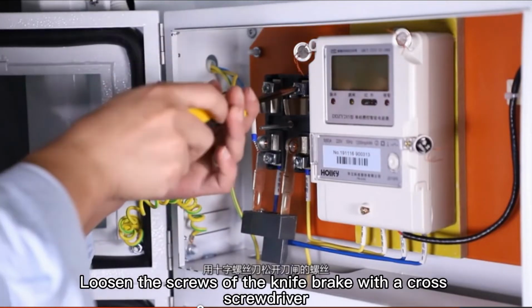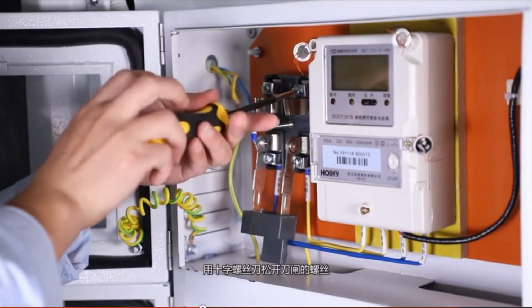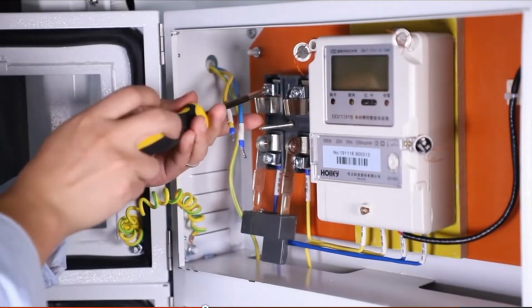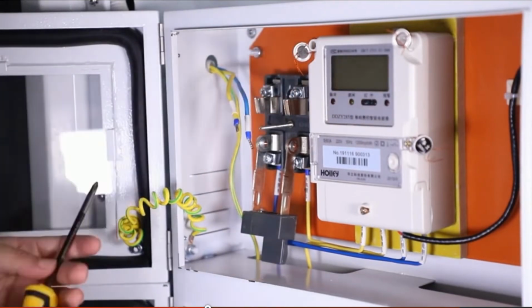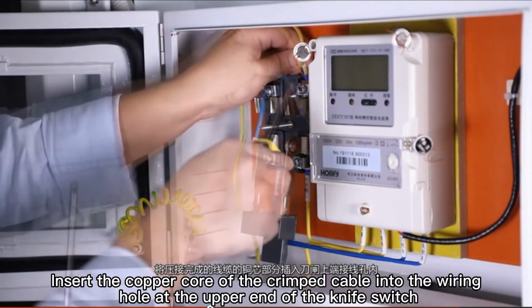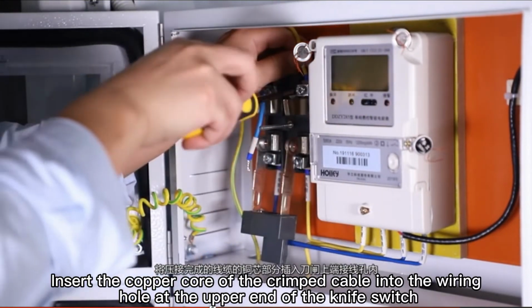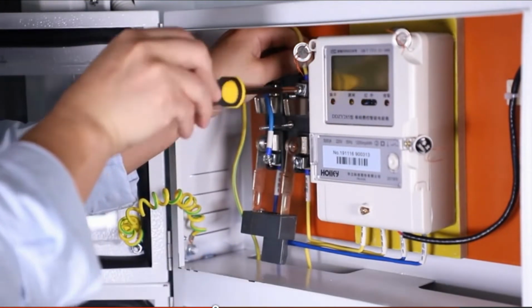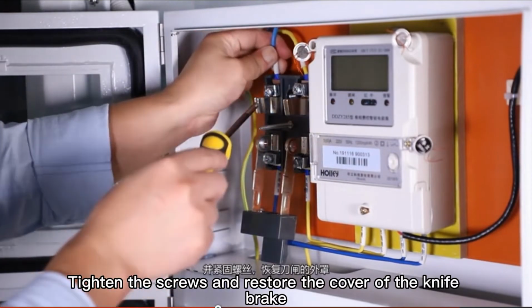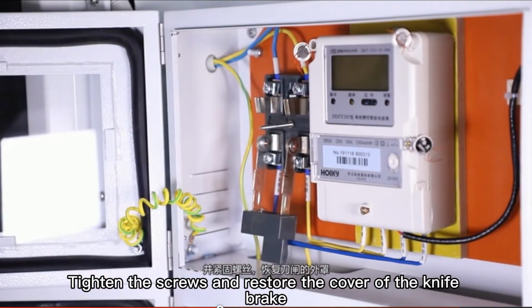Loosen the screws of the knife switch with a cross screwdriver. Insert the copper core of the crimped cable into the wiring hole at the upper end of the knife switch. Tighten the screws and restore the cover of the knife switch.